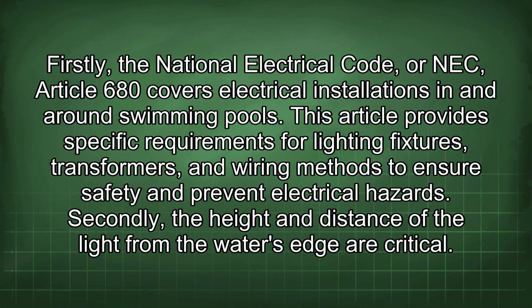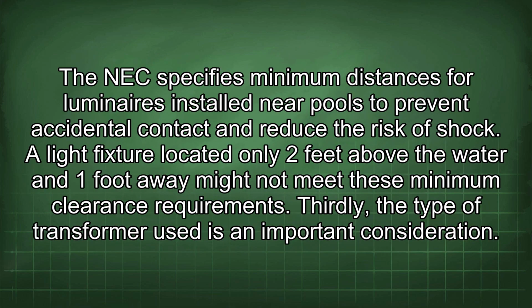This article provides specific requirements for lighting fixtures, transformers, and wiring methods to ensure safety and prevent electrical hazards. Secondly, the height and distance of the light from the water's edge are critical. The NEC specifies minimum distances for luminaires installed near pools to prevent accidental contact and reduce the risk of shock. A light fixture located only 2 feet above the water and 1 foot away might not meet these minimum clearance requirements. Thirdly, the type of transformer used is an important consideration.